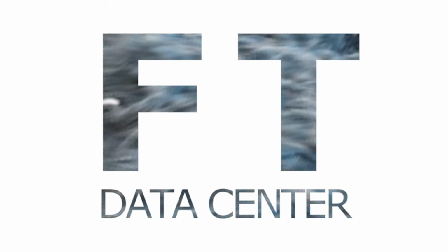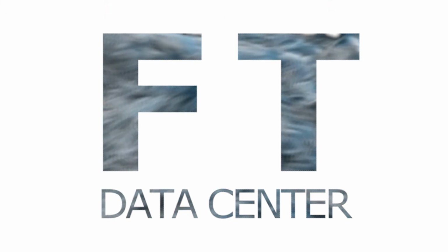Drew here. A few years ago, I went into a client's data center because they were having airflow problems. I took one look at their setup and gave them the answer. They didn't hire me because the fix was so easy. What was the problem? Well, their vented floor tiles were too close to the nearest CRAC unit. I actually took a piece of paper and put it over top of the vented tile, and it was sucked down towards the floor. So the question is, why?